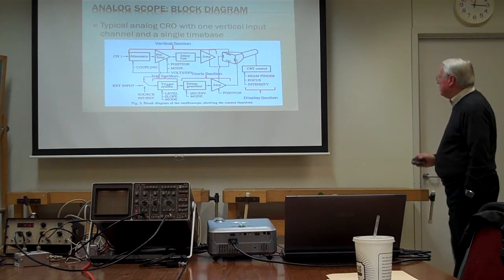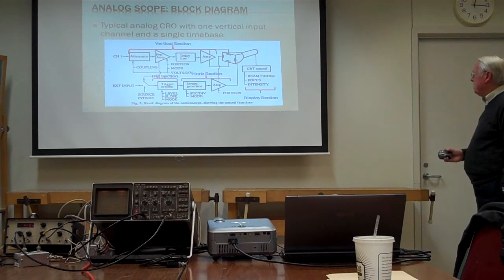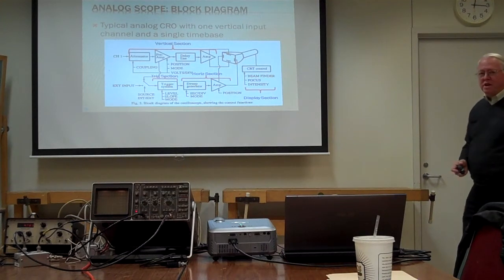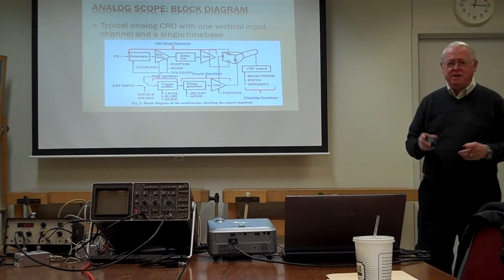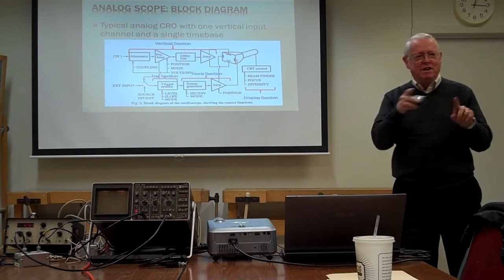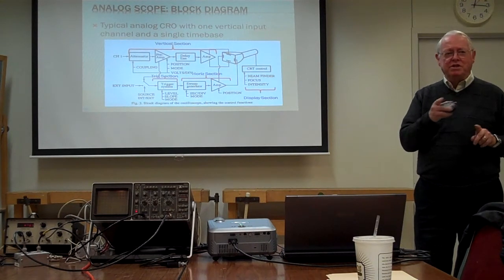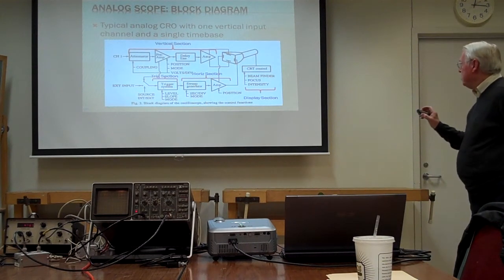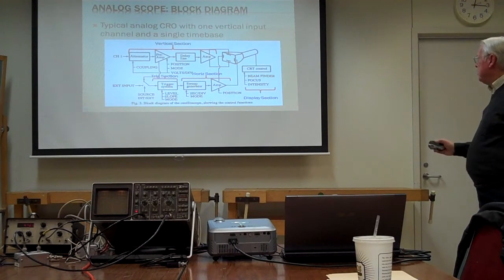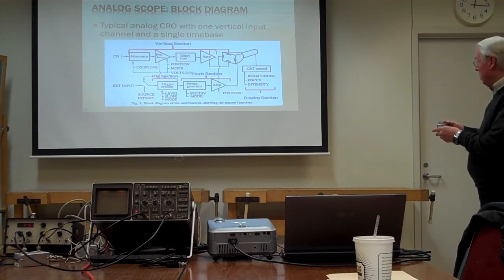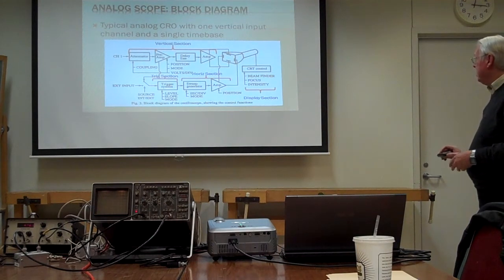CRT control has some different functions as part of the display section on the scope. You have a beam finder — if some signal comes in and you don't know where the beam is, you can hit it and it'll drag the beam back to center so you know where it is. Also, focus control and intensity are other controls there.